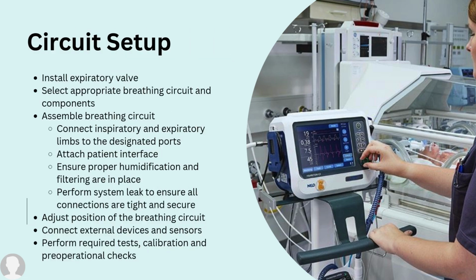Here are the steps for the circuit setup. First, we must install the expiratory valve and select the appropriate breathing circuit and components. To assemble the breathing circuit, we must connect the inspiratory and expiratory limbs to the designated ports and attach the patient interface. We must ensure there's proper humidification and filtering in place and perform a system leak test to ensure that all connections are tight and secure.